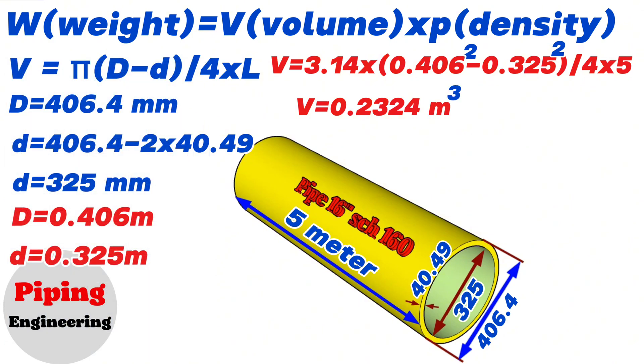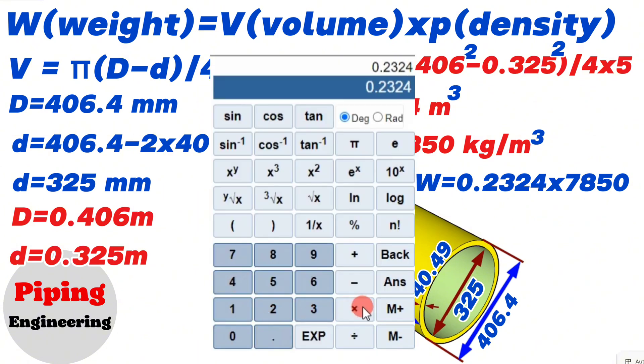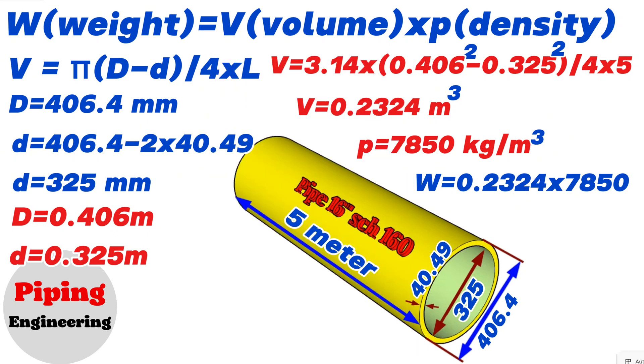We already know that the iron steel density is 7850 kg per cubic meter. Now let's write this into the weight calculation formula. Weight equals volume 0.2324 cubic meters multiplied by the density 7850 kg per cubic meter. Using the calculator, we find that 0.2324 × 7850 equals 1824. So the weight of the 16 inch schedule 160 pipe in our example is 1824 kg.